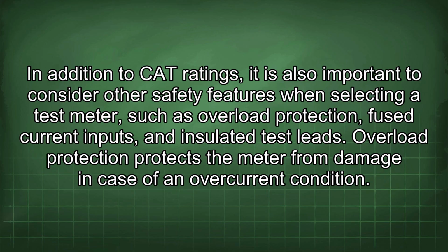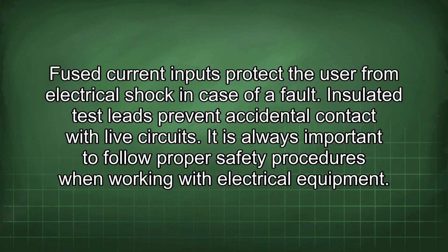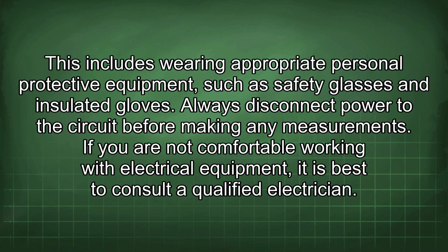In addition to CAT ratings, it is also important to consider other safety features when selecting a test meter, such as overload protection, fused current inputs, and insulated test leads. Overload protection protects the meter from damage in case of an overcurrent condition. Fused current inputs protect the user from electrical shock in case of a fault. Insulated test leads prevent accidental contact with live circuits. It is always important to follow proper safety procedures when working with electrical equipment. This includes wearing appropriate personal protective equipment, such as safety glasses and insulated gloves. Always disconnect power to the circuit before making any measurements. If you are not comfortable working with electrical equipment, it is best to consult a qualified electrician.